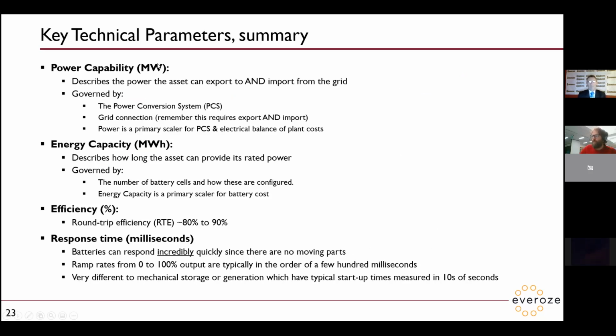But there's more than that. We've talked about power, megawatts, and that's governed to some extent by the batteries, but more by things like your power conversion system (PCS), your transformers, your switchgear, and your grid connection. Most projects will be sized to deliver all the power their grid connection will allow, or import all the power their grid connection will allow.